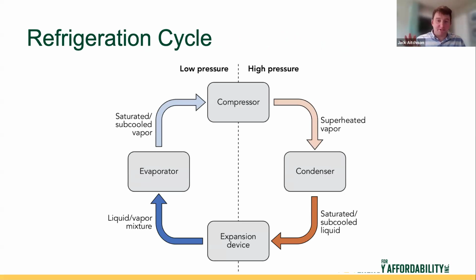Just real basic, just to understand how a heat pump works and the use of a refrigeration cycle. So this is a basic diagram of a refrigeration cycle. Start on the left with the evaporator. What the evaporator does is change that refrigerant from a liquid/vapor mixture into a vapor. And when it goes through that phase change, when it evaporates, it's going to pull in heat from the surrounding air. Then it's going to go through a compression cycle.